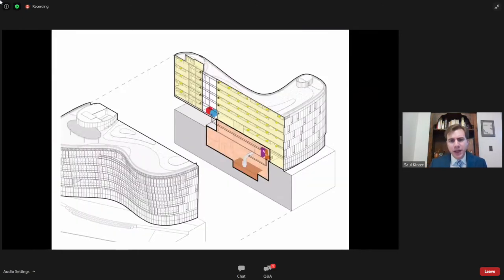So this is a cutaway of the building, and you can see in the pink down at the bottom is the pre-existing sewage pump station, so occupying a big chunk of the first floor and then going down underground. And the white pipe there is actually the outlet pipe. It's the main outlet for the sewage pump station. So all we did to access the sewage was put a bulkhead on a sideline off that pipe and then put a pump next to it. So the sewage just gets pumped straight out of the outlet line when the building has a need for it. It gets lifted up about 20 feet into a utility room where we have a heat exchanger. That heat exchanger then extracts energy from the sewage and it drops right back down into the outlet line. It's a really simple system.